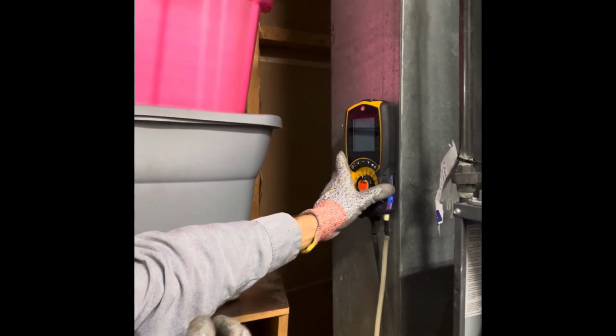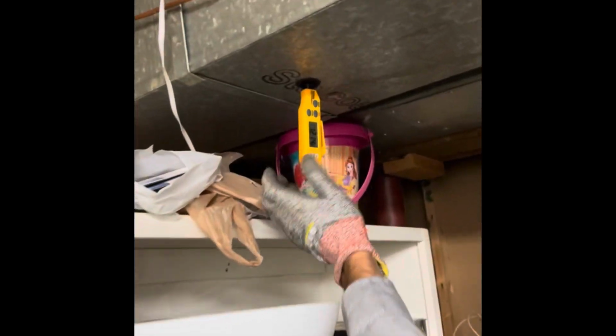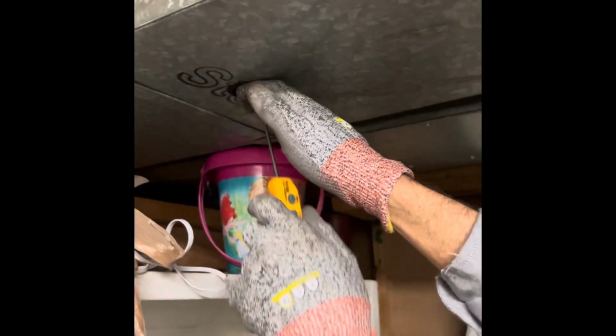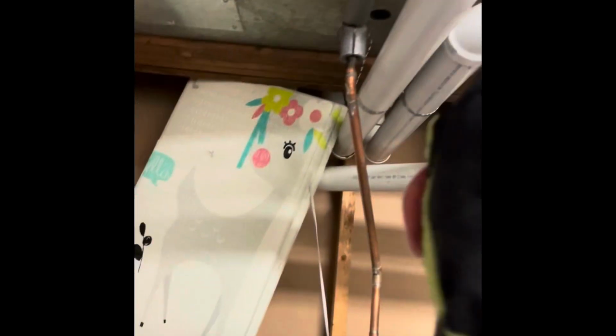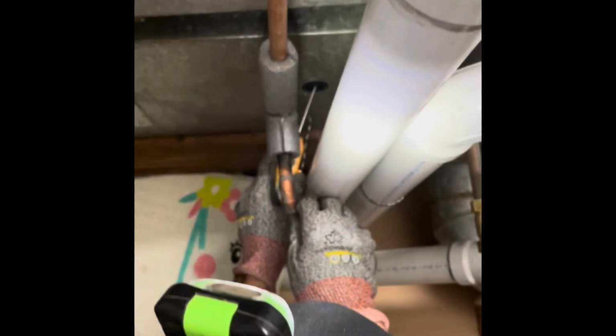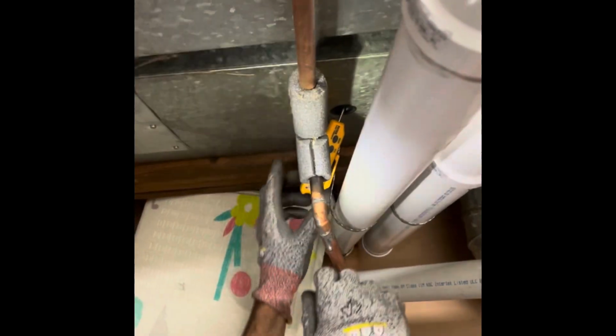So I'll just leave that there for a minute. I want to see what my temperatures are doing. If we look over here, I've got a supply air temperature of 121. And now we've got to take a return air measurement. So I'm going to go right back in here with the return. There's a little duct cleaning plug. That's going to take a bit for our temperatures to come down, so we'll let that stabilize.